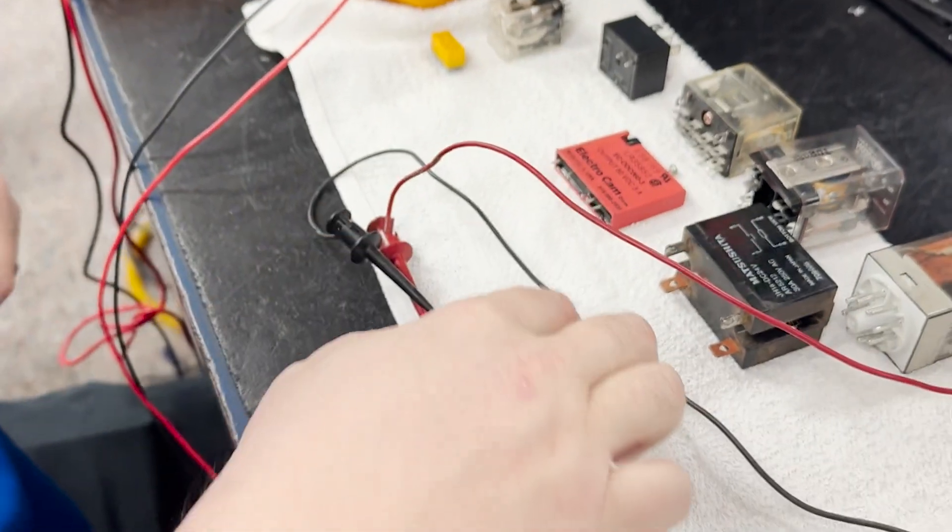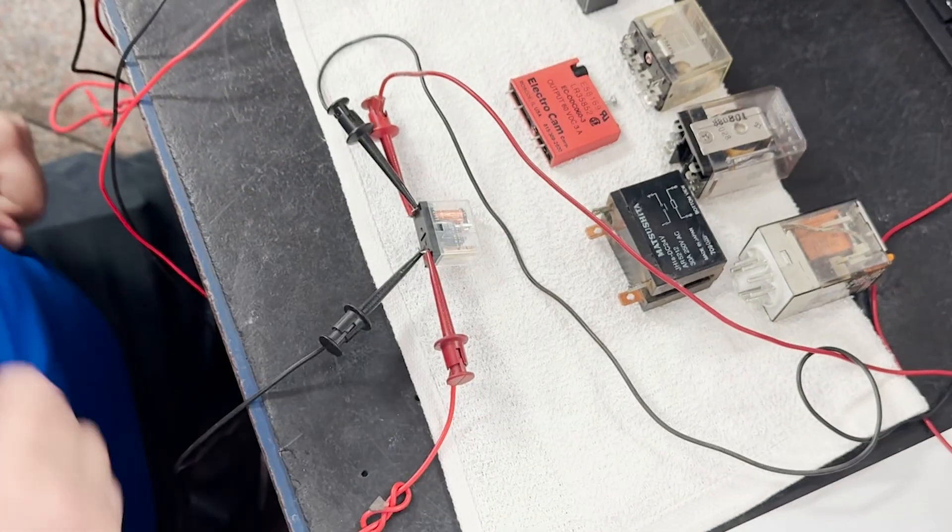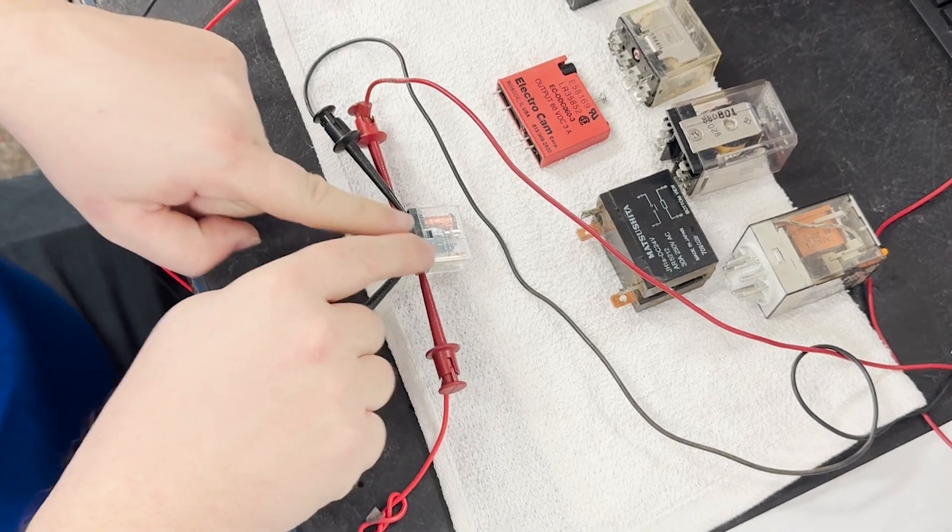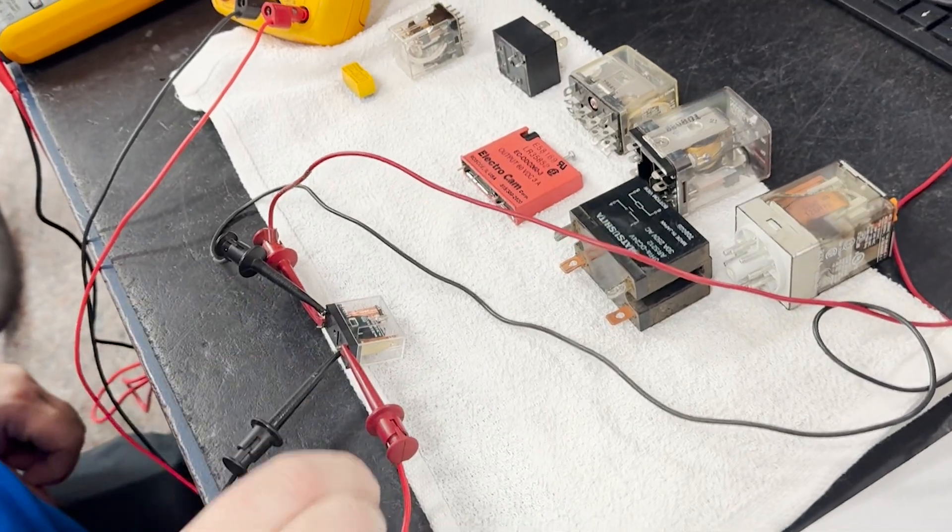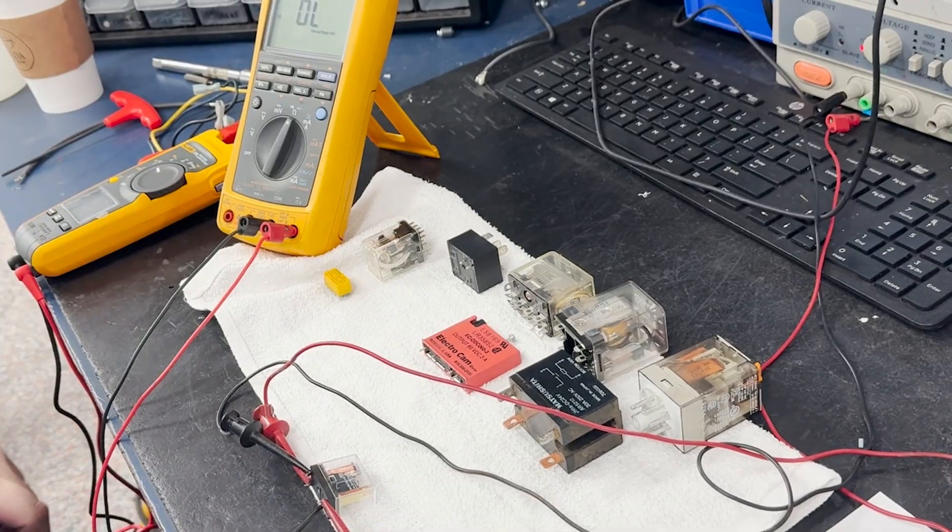Whenever you encounter a non-functioning relay, you should measure the coil. If the coil measures good, there's either a problem with the relay or it may be a polarized relay and you need to take that into consideration.